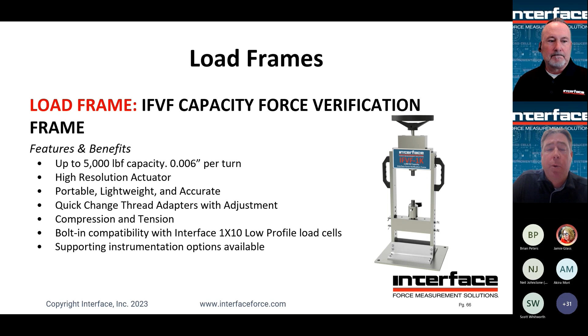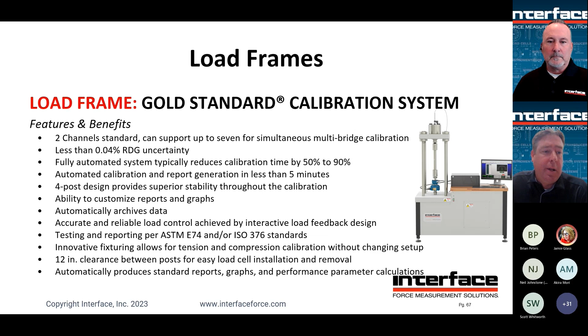We do offer calibration load frames. So these are essentially completely self-contained calibration systems with a hydraulic power unit on the right hand and a piston on the left hand of that frame, designed around a very specific and very precisely aligned set of platens and columns. We use a 4-column design for stiffness, and have a unique load string system that allows us to load both tension and compression without having to break the load string. This will let you run a calibration run in less than 5 minutes, including report generation. For most folks, that reduces the calibration time by 50 to 90%. So about a 12-inch post-to-post clearance for load cell and DUT installation. And again, that's automatic report generation, and archive is a real time saver for most folks.